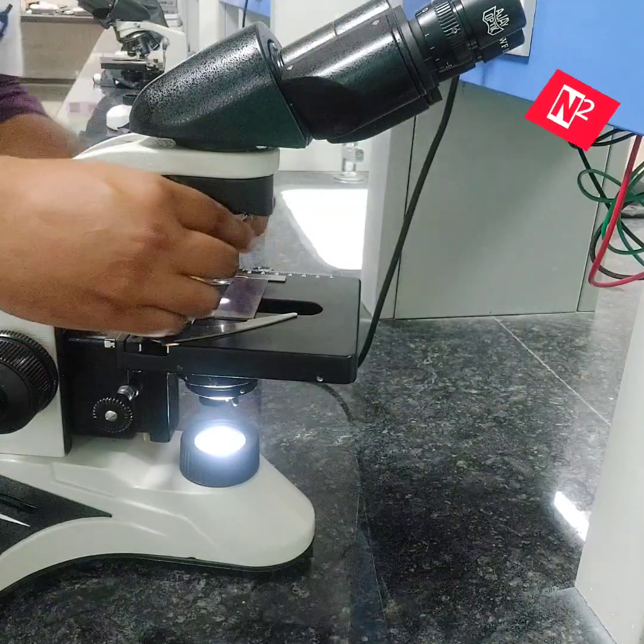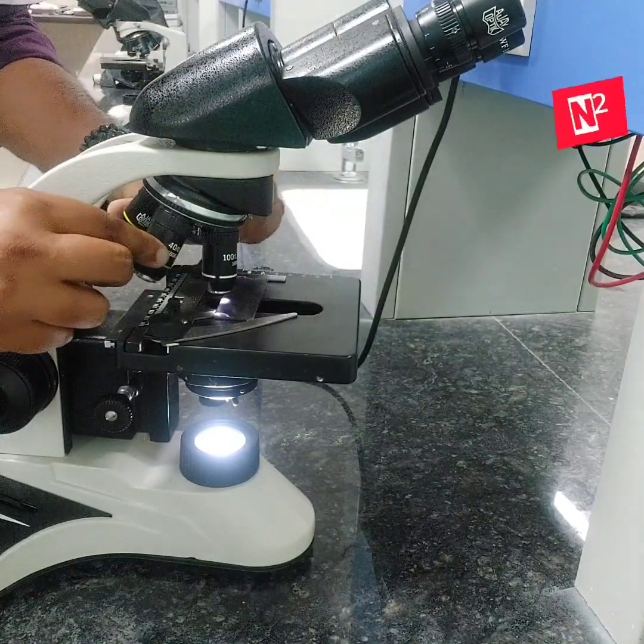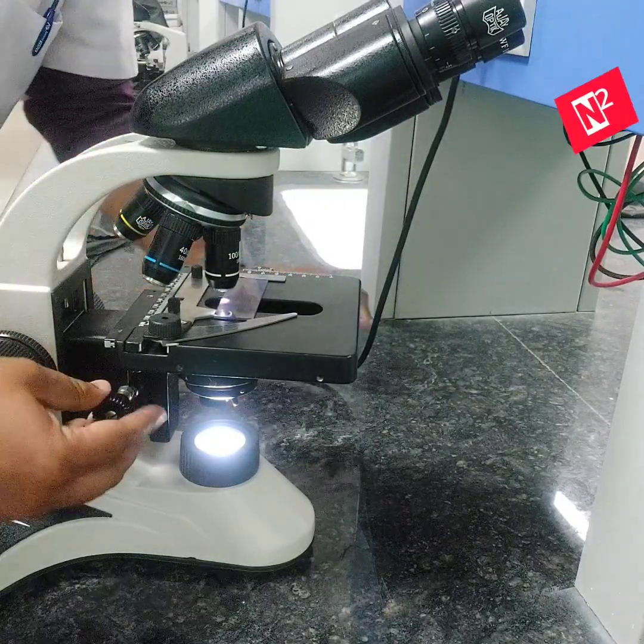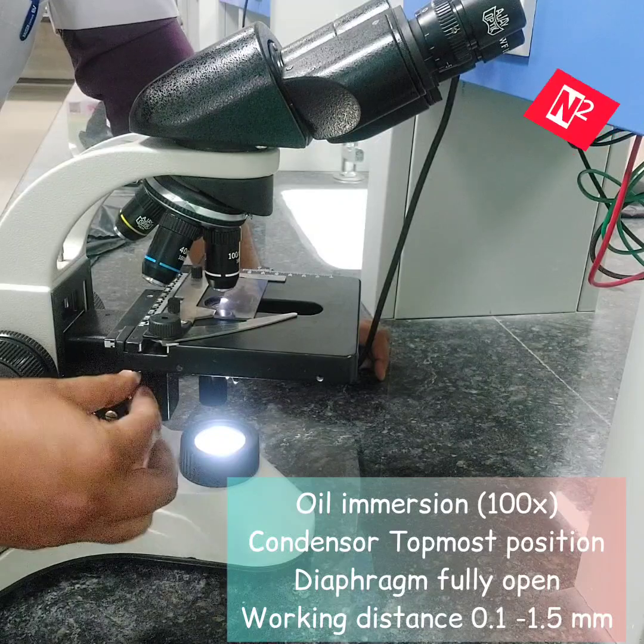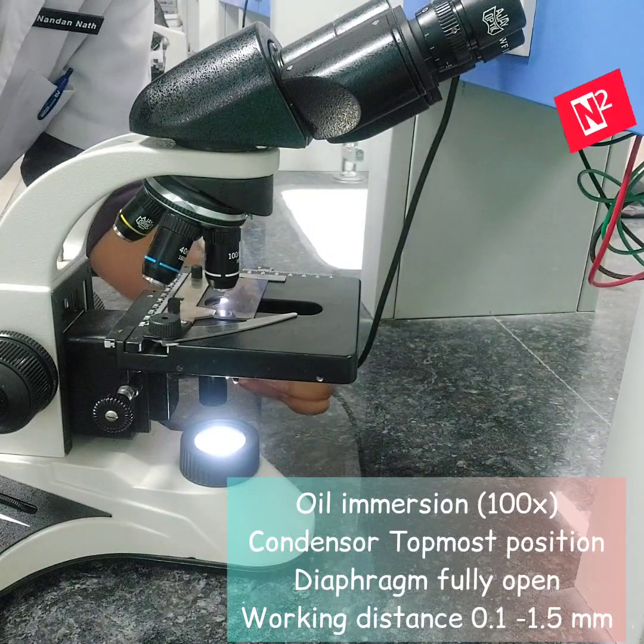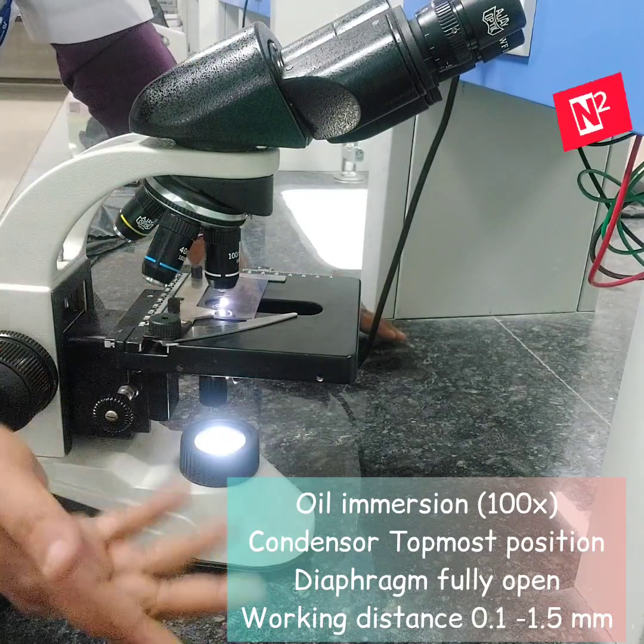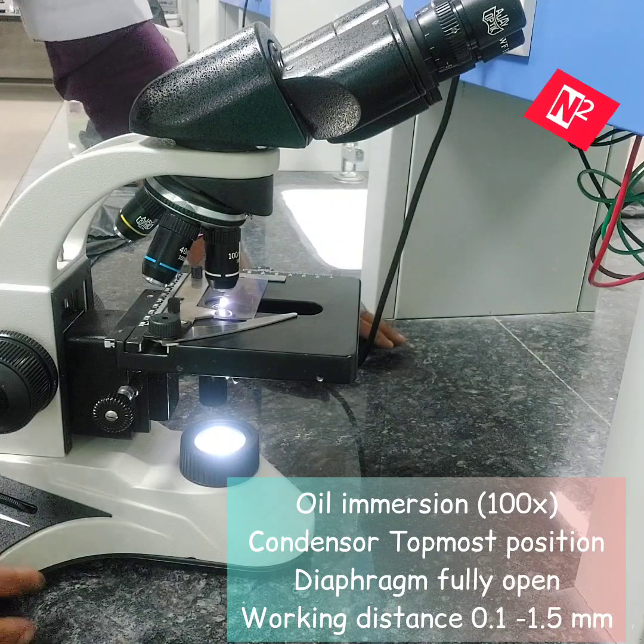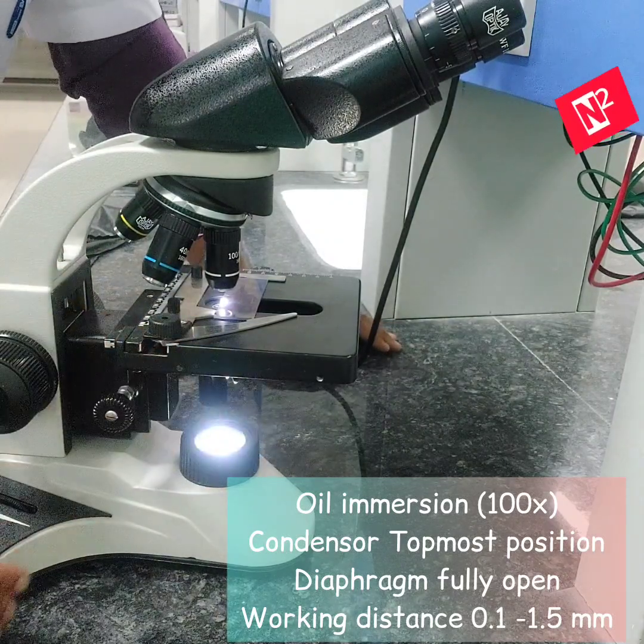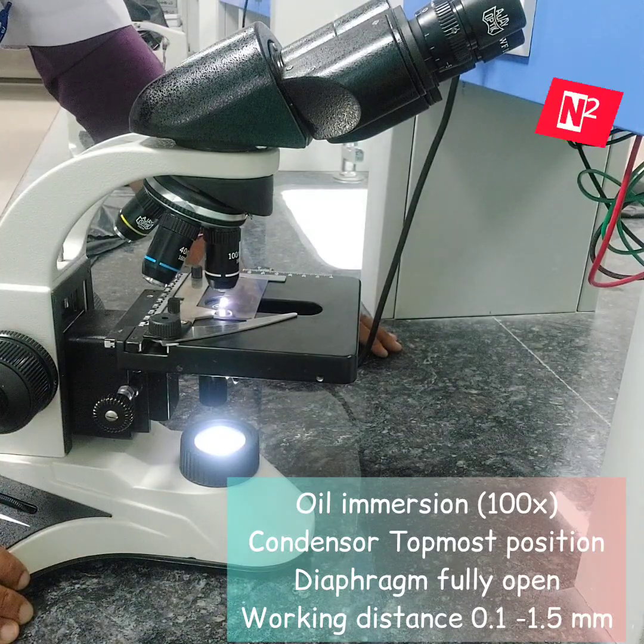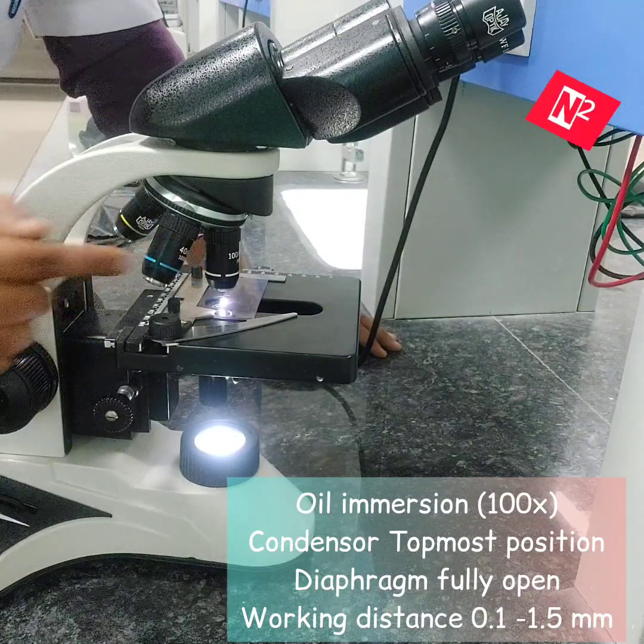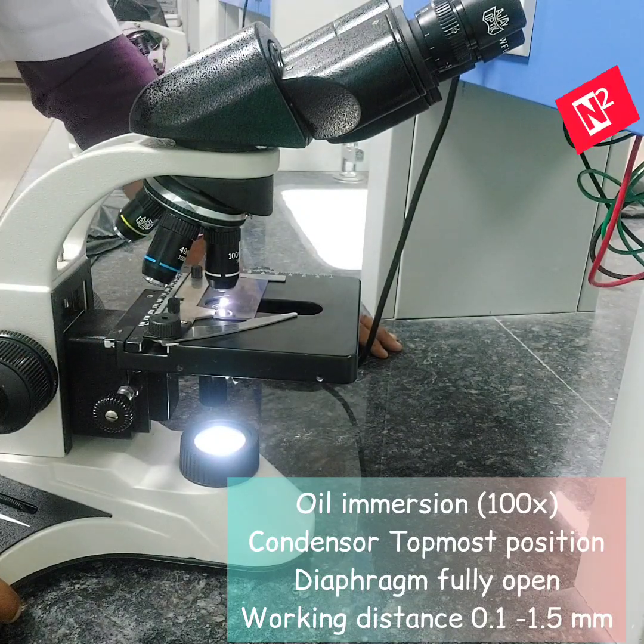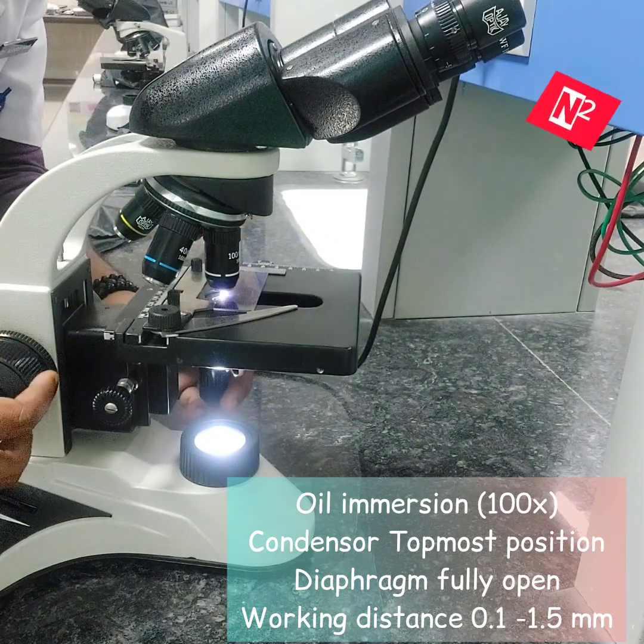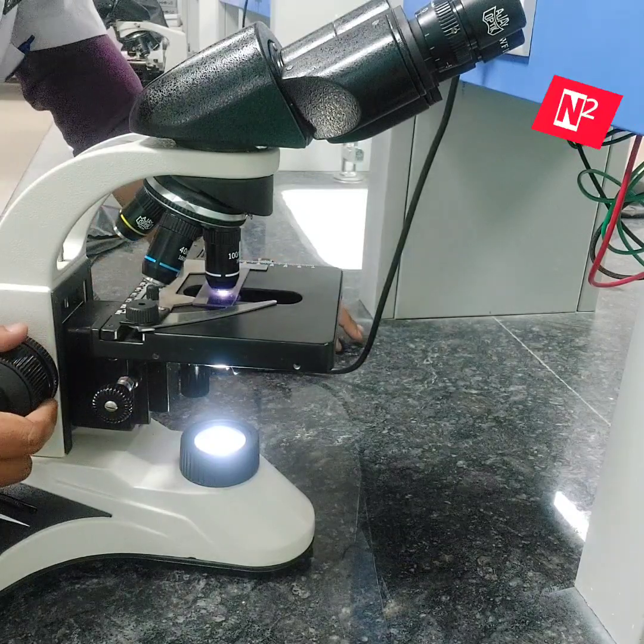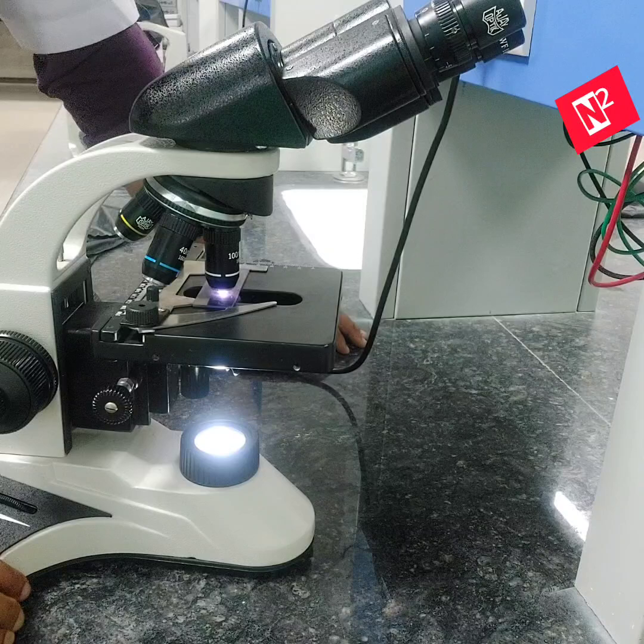While you are using the oil immersion, what are the positions? Let's bring in the oil immersion lens, 100x. When you bring the 100x lens into position, the condenser should be at the topmost position possible, and you fully open the iris. This is the recommended position, based upon your vision and feasibility. You can do minor adjustments, but these are the guidelines for using the microscope. The working distance now decreases to 0.15 to 1.5 millimeter. The lens is absolutely close to the glass slide, almost touching, but there will be some potential space of 0.1 millimeter.